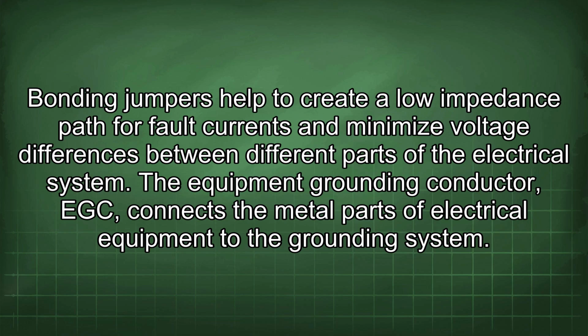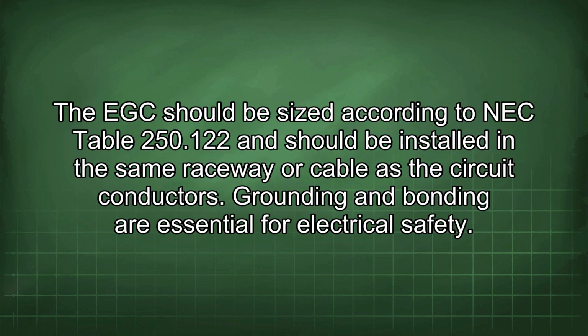The equipment grounding conductor (EGC) connects the metal parts of electrical equipment to the grounding system. The EGC should be sized according to NEC Table 250.122 and should be installed in the same raceway or cable as the circuit conductors.